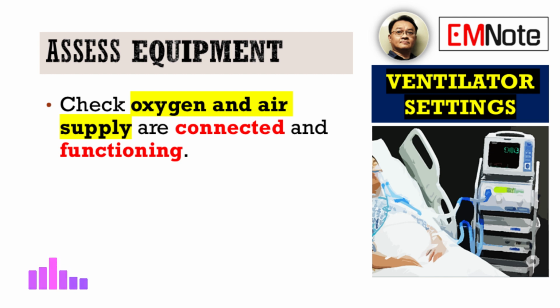And beyond just checking the connection, you need to confirm these gas supplies are functioning correctly. Are they providing consistent flow, appropriate pressure? This usually involves checking the pressure gauges, either on the wall outlets or maybe the gas cylinders themselves. You need to ensure they're delivering the required pressure. That's typically between 50 and 60 pounds per square inch, or psi, to the ventilator.